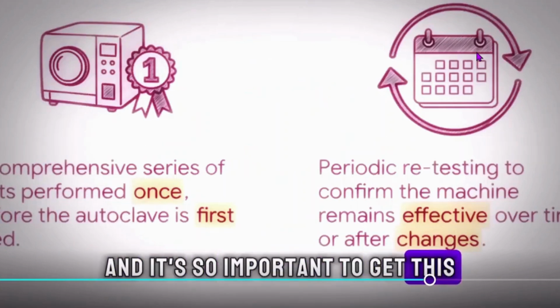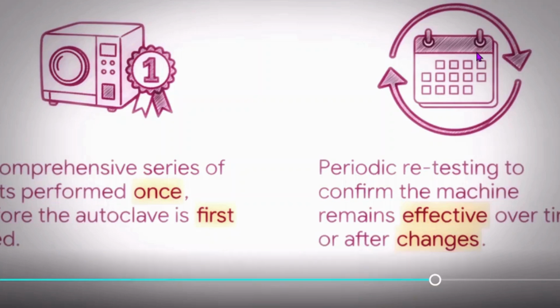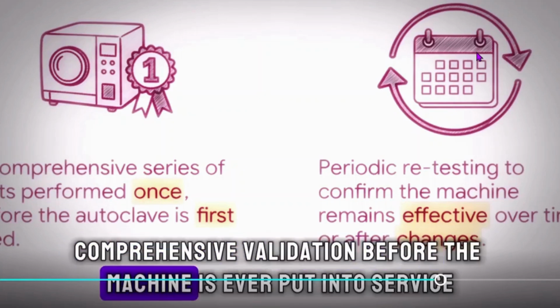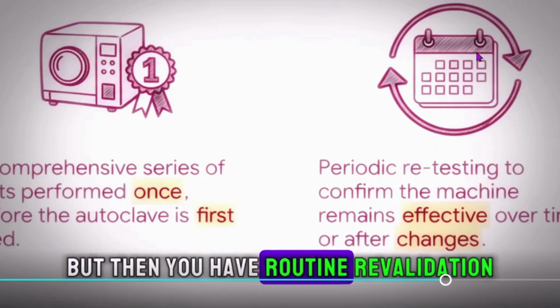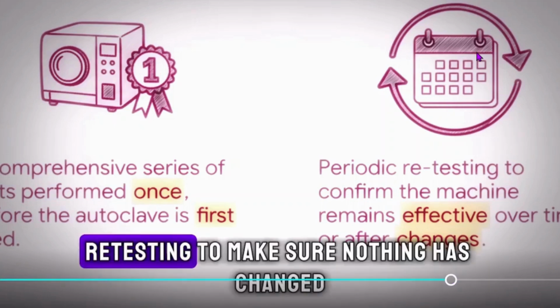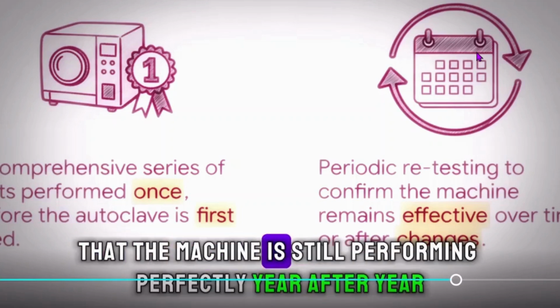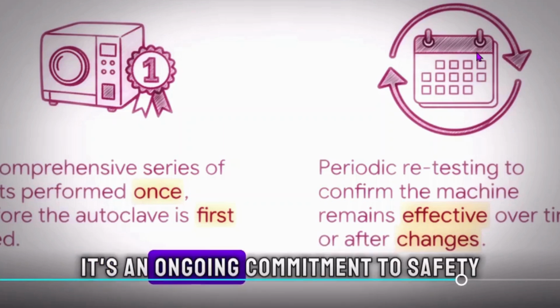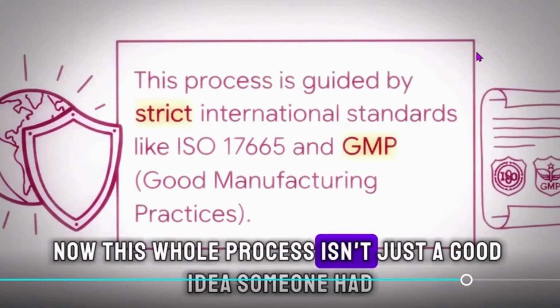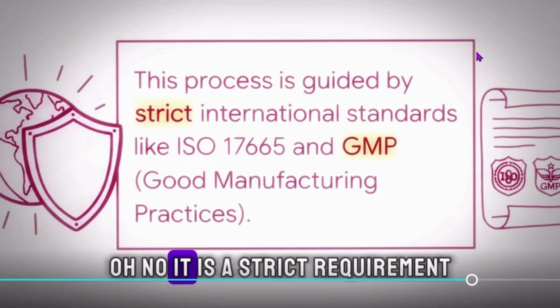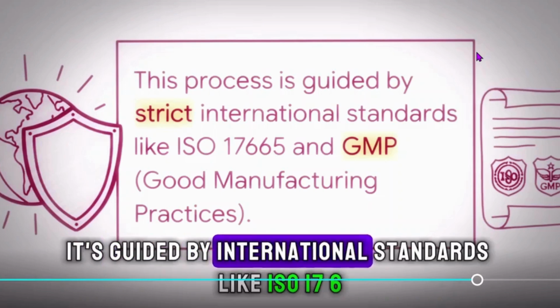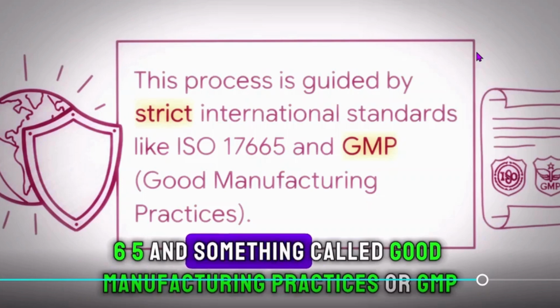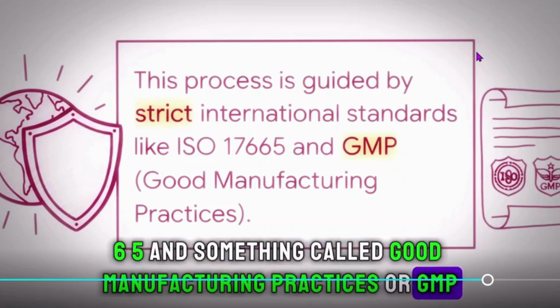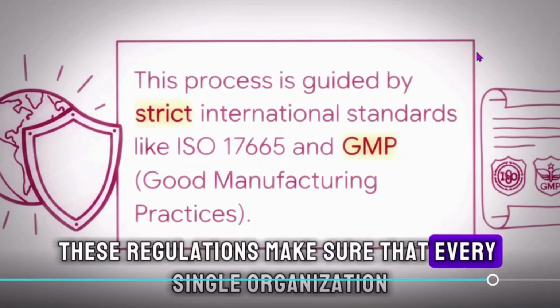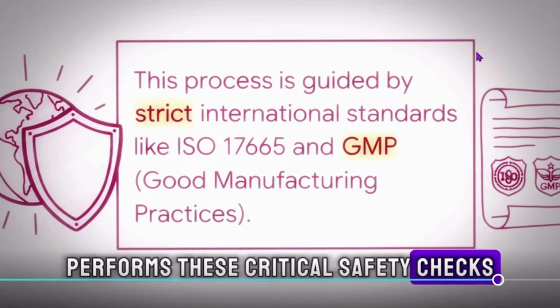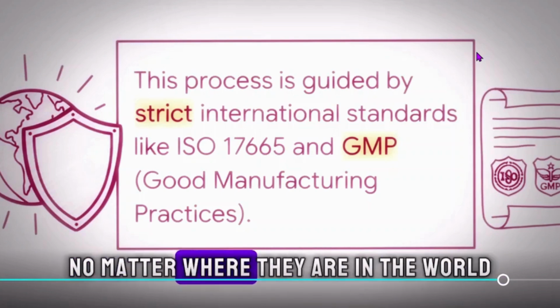And it's so important to get this. Validation is not a one-and-done deal. You have that initial, super comprehensive validation before the machine is ever put into service. But then you have routine revalidation. That means you're periodically retesting to make sure nothing has changed, that the machine is still performing perfectly year after year. It's an ongoing commitment to safety. Now, this whole process isn't just a good idea someone had. Oh no. It is a strict requirement. It's guided by international standards like ISO 17665 and something called Good Manufacturing Practices, or GMP. These regulations make sure that every single organization performs these critical safety checks to the exact same high standard, no matter where they are in the world.